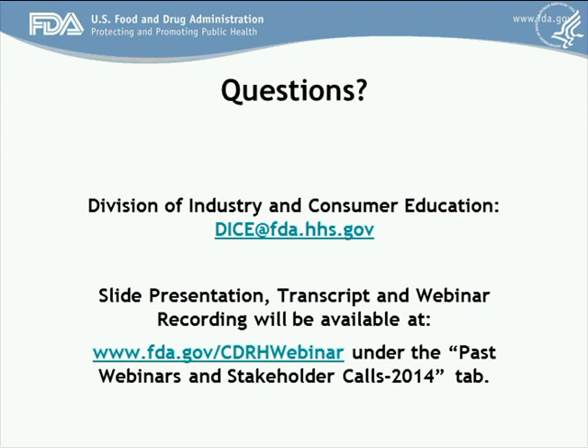There was a question somewhat like this earlier, but I think this is slightly different. Are the cybersecurity guidelines applicable to mobile apps that are subject to enforcement discretion? Mobile apps that are subject to enforcement discretion are exempt from the FD&C Act, so there will be no submission required, and no submission that the FDA would be reviewing. At the same time, just as a general practice, we would encourage you to consider cybersecurity as part of your risk assessment, regardless of whether the FDA will see that submission or not.